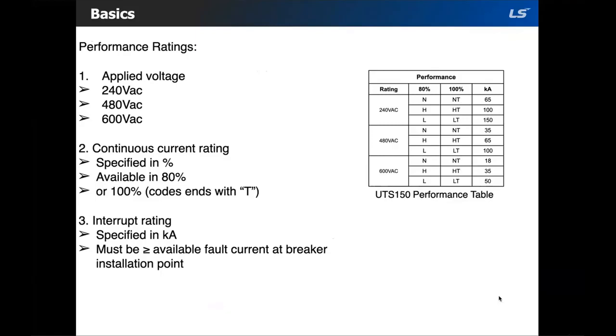So as you can see in this table, 80% performance is indicated with the N, H and L. And if you need the breaker at 100% performance, it would be indicated with the T at the end. So the third thing you must know to specify an MCCB is the interrupting rating. The interrupt rating, typically specified in kA or kiloamperes, is the amount of fault current the breaker can safely interrupt without damaging itself. As you can see in the table, the interrupt rating decreases as the voltage increases.